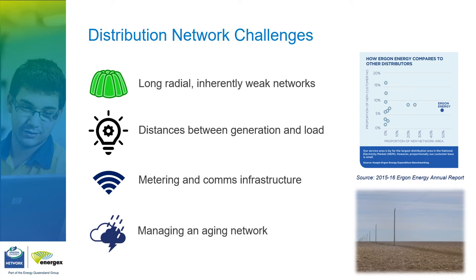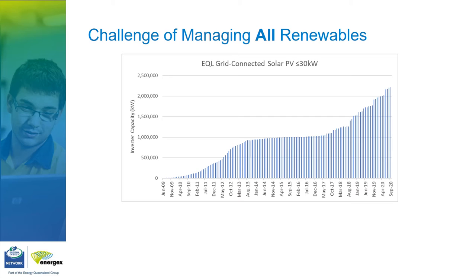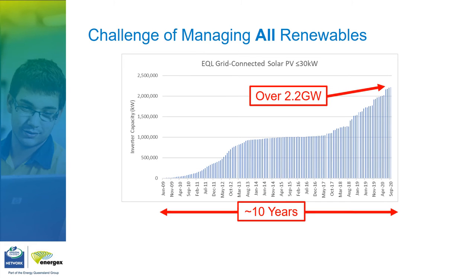And like many DNSPs, we are managing an aging distribution network in areas that are really prone to cyclones and things like bushfires as well. So that in itself is a big challenge, let alone the challenges of renewable connections on top of that again. So in the recent AEMC final report on the system strength framework, it identified system strength is not an issue on the LV distribution network by virtue of the connection back onto the HV, a much more stable source. However, despite this, there has been significant growth in residential solar PV over the last decade, as we all know. And we find that over the last 10 years, we've gone up to over 2.2 gigawatts of grid-connected residential solar, less than 30 kilowatts.